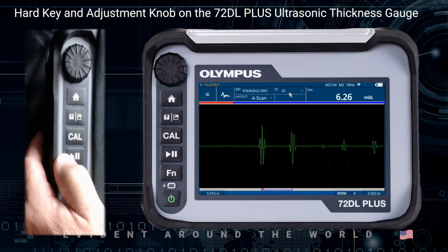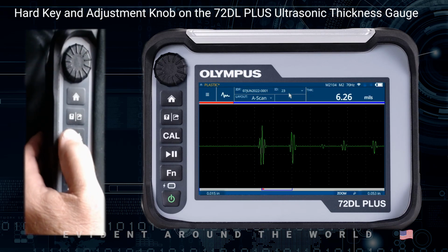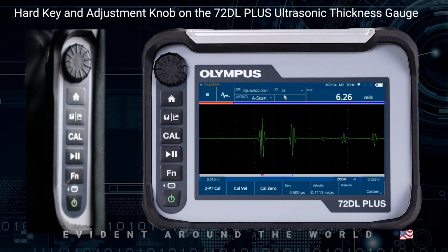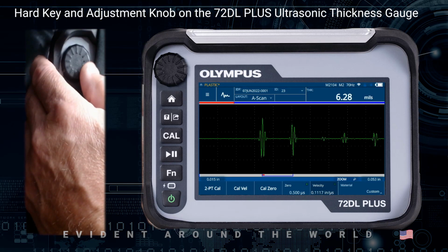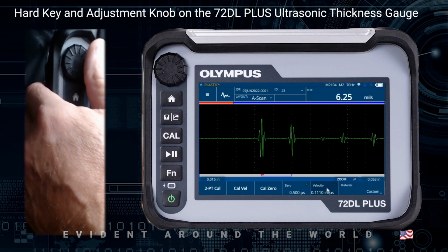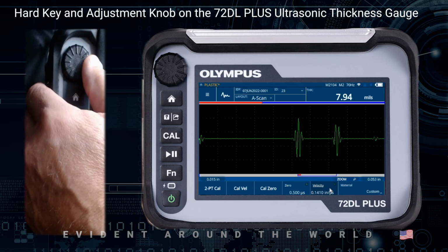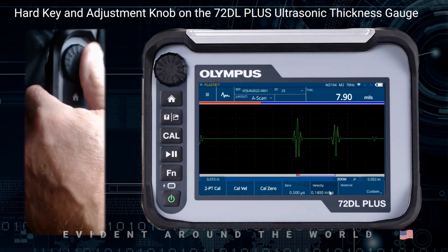Below the save send key is the cal key. Pressing the cal key will bring up the calibration items and menu. In this menu, you have the ability to perform or start a 2-point calibration, a single point velocity calibration, or a single point zero calibration. It allows you to manually adjust the zero value and the velocity value. Again, simply clicking on it and then adjusting it with the knob will allow me to increase or decrease that value. Again, a double click is a coarse adjustment. A single click gives me a fine adjustment.